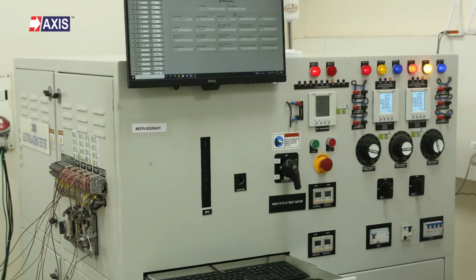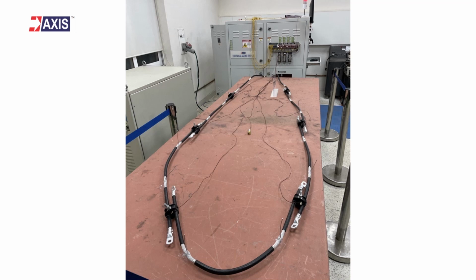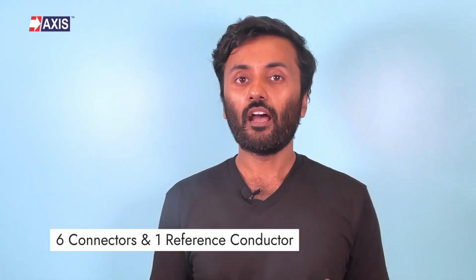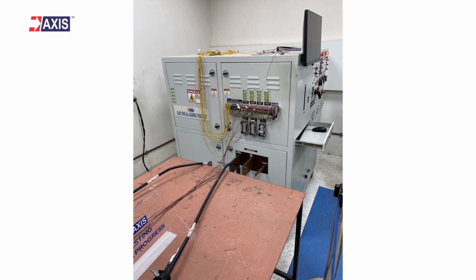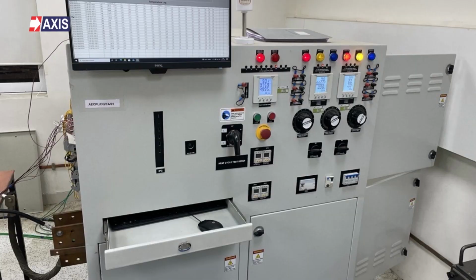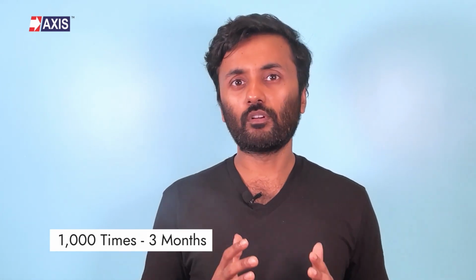Now, the last test, the electrical aging test. The goal of this test is to assess the connector's long-term performance, which is absolutely critical for long-term use in harsh environments. We connect multiple IPC samples with appropriate cables in a series to form a test loop. We then evaluate the functional properties of 6 connectors and 1 reference conductor. This reference conductor is part of the loop, and we control its temperature to reach 120 degrees Celsius by injecting current. After both the connector and the reference conductor are heated and stabilized, they are cooled back to ambient temperature. We repeat this heating and cooling cycle 1000 times, which takes approximately 3 months to complete. The Axis IPC passes the test if it meets the standard criteria as per NFC 33020 standard for resistance and temperature, proving that the Axis IPC is built for longevity.